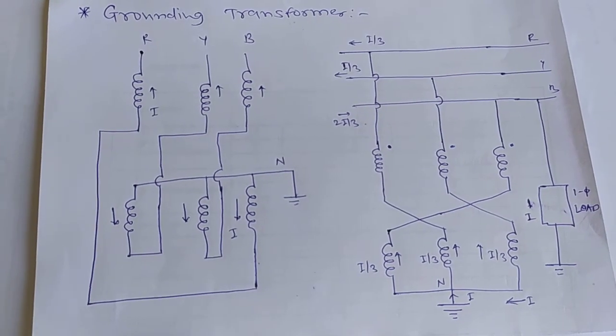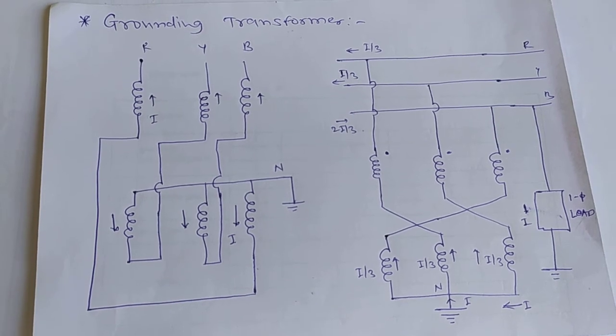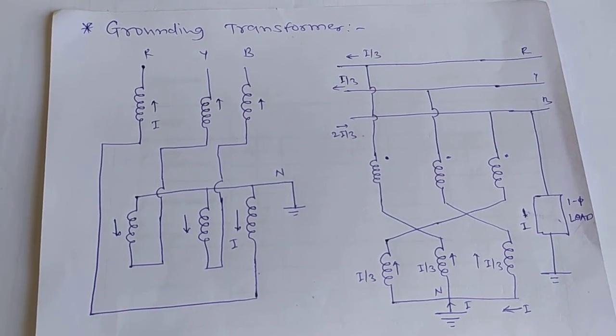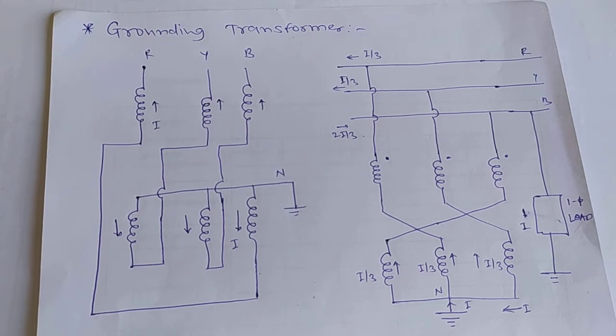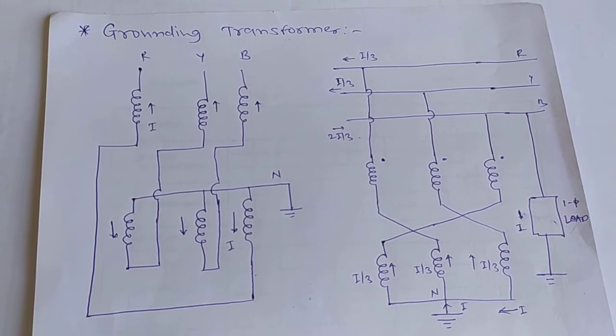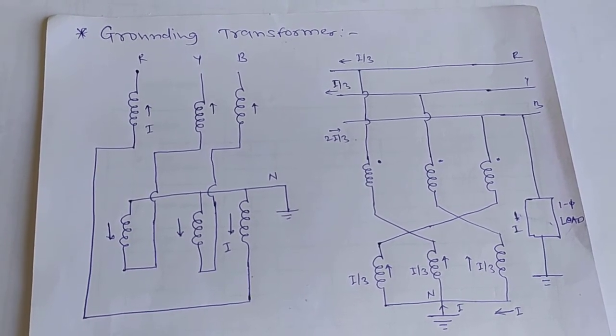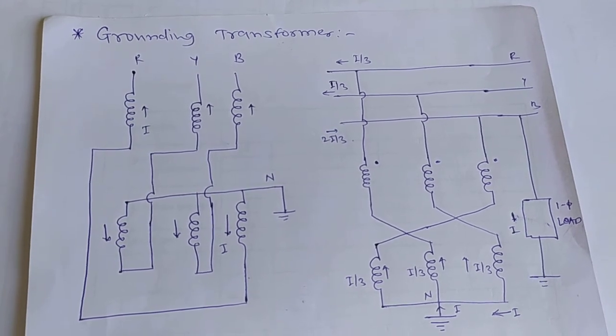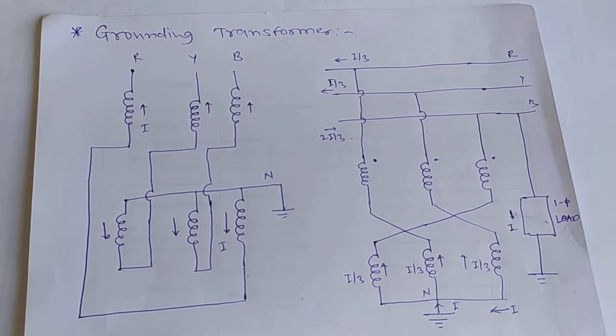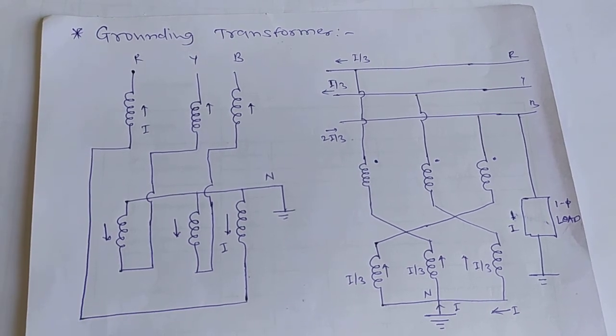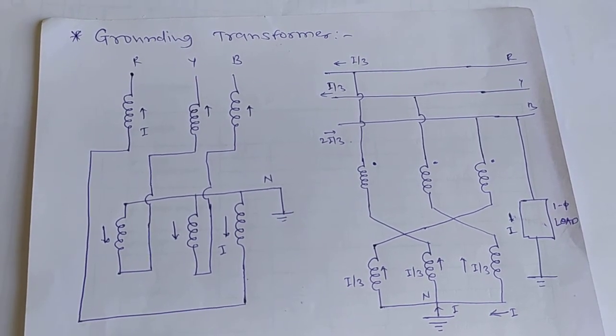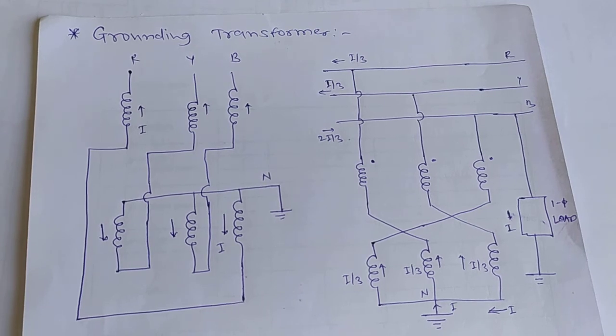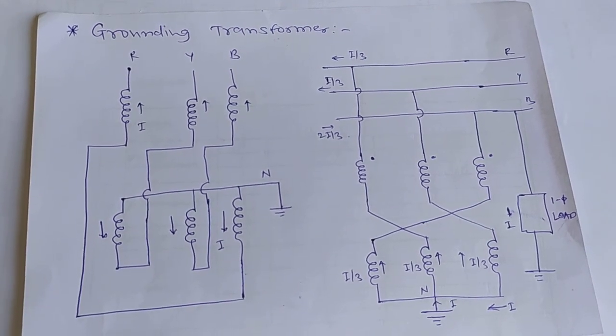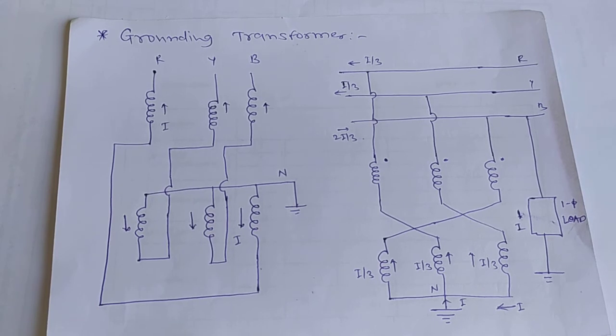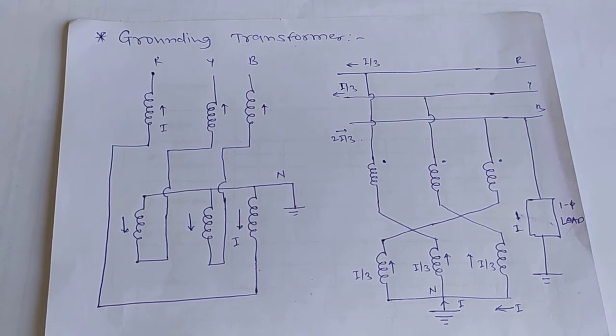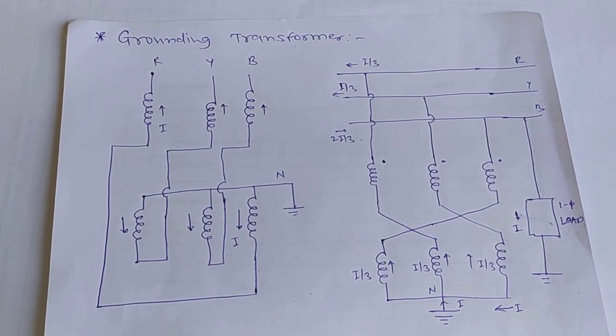The second figure shows the use of a grounding transformer to create a neutral point N. If we connect a single phase load between one line and neutral as shown in the figure, the load current I is divided into 3 equal parts in each winding. Because the currents are equal and the neutral point stays fixed, the line to neutral voltages remain balanced as they would be on a regular 4-wire system.